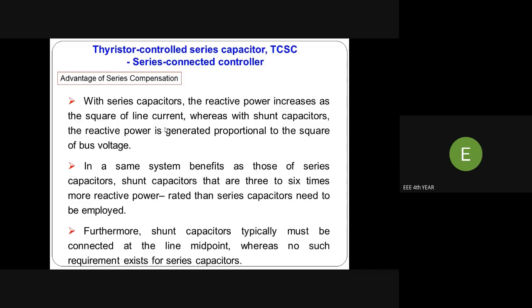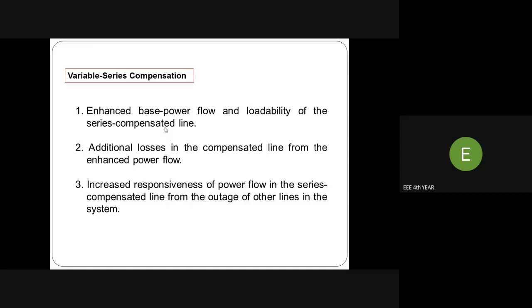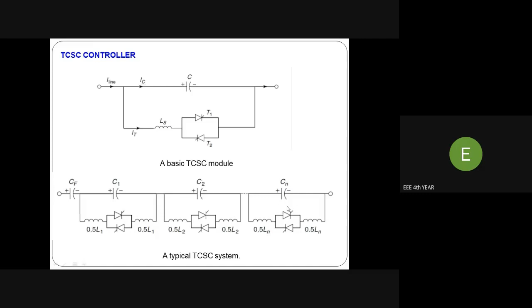It is a variable series compensation: enhanced power flow, loadability of the series compensated transmission line, additional losses in the compensated line from the enhanced power flow, and increased responsiveness of the power flow in the series compensated line to the outages of other lines in the system. It can be a single unit or multiple units of TCSC. The diagrams show a basic TCSC module and multiple units of TCSC modules. Up to n number of TCSCs can be implemented in series with the transmission line, as required.